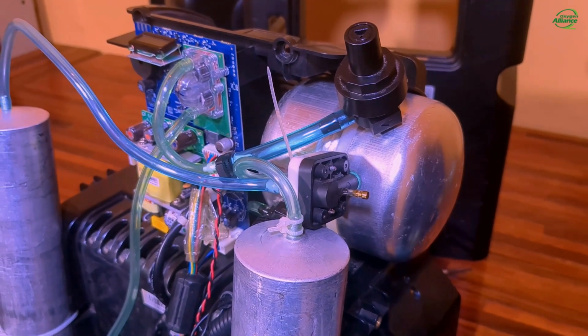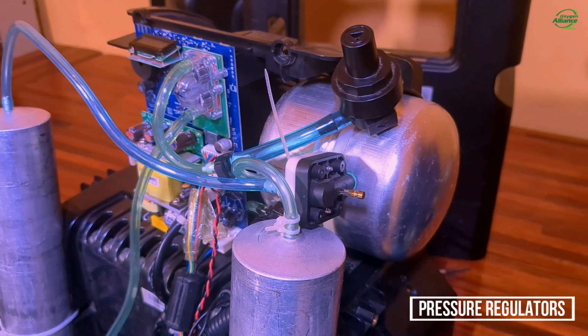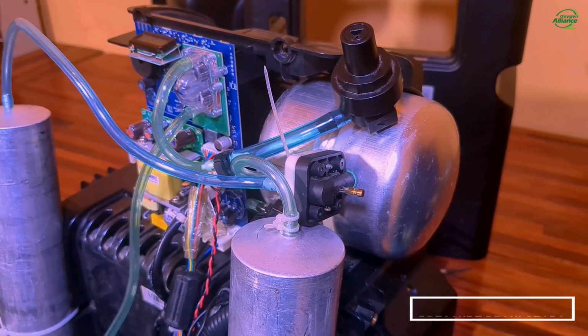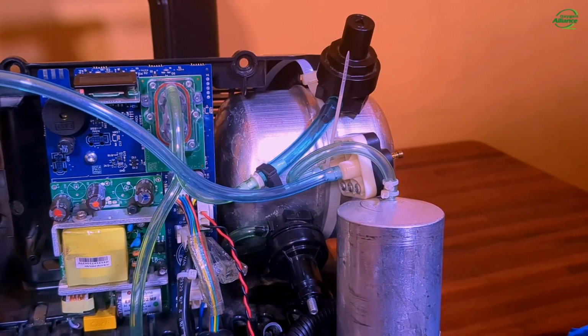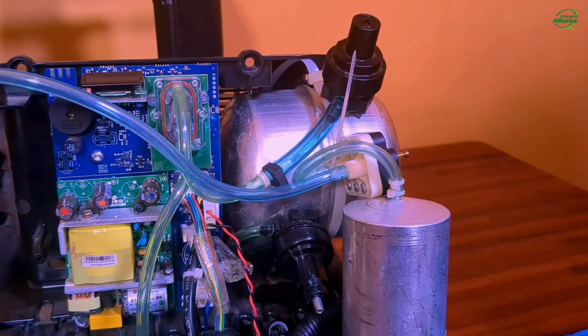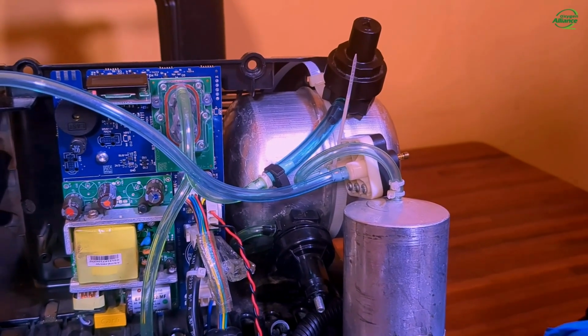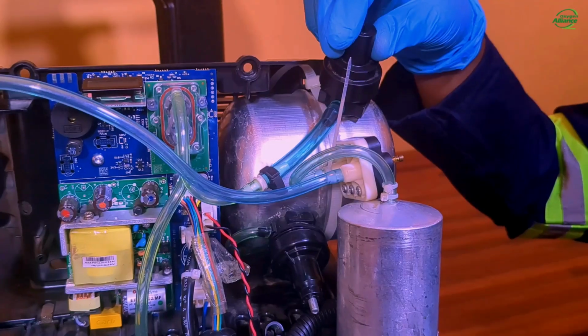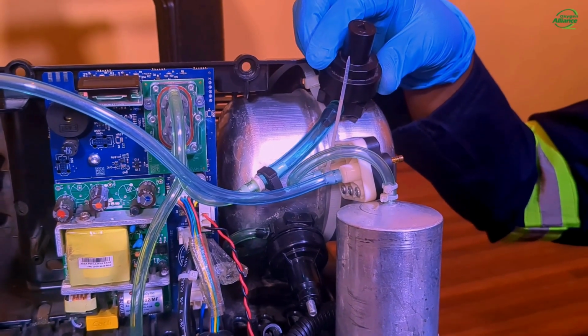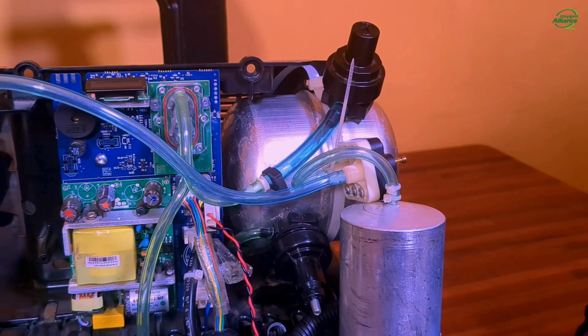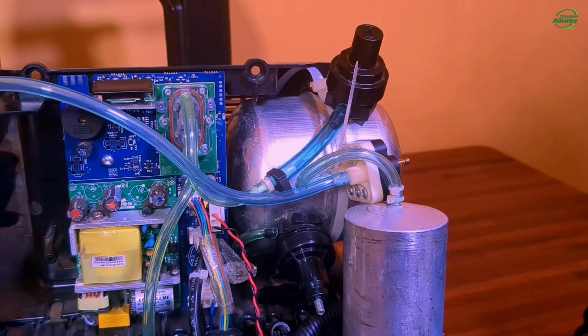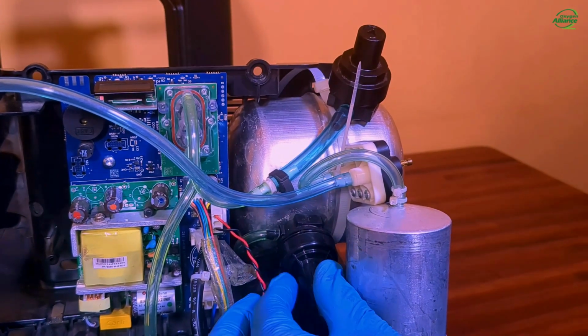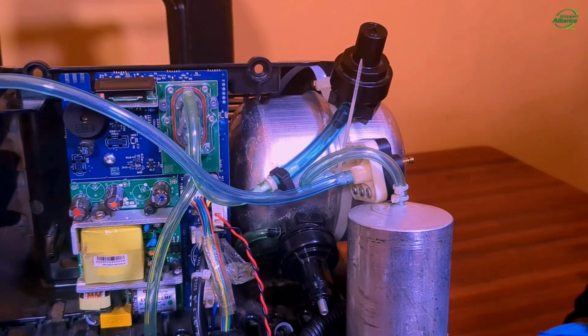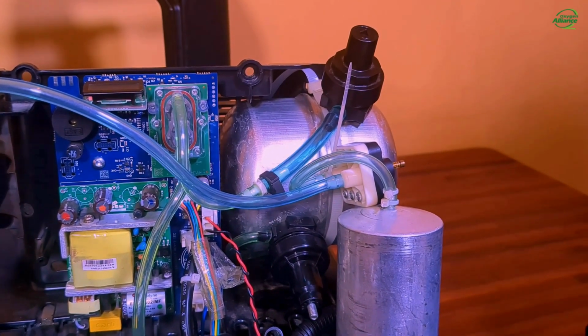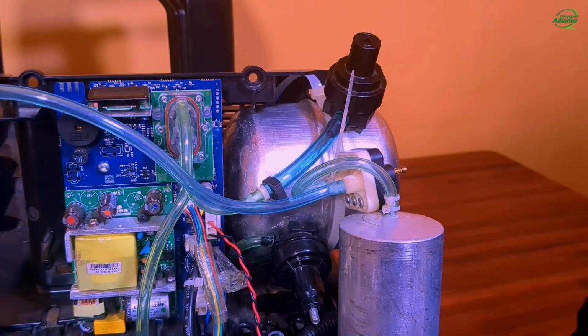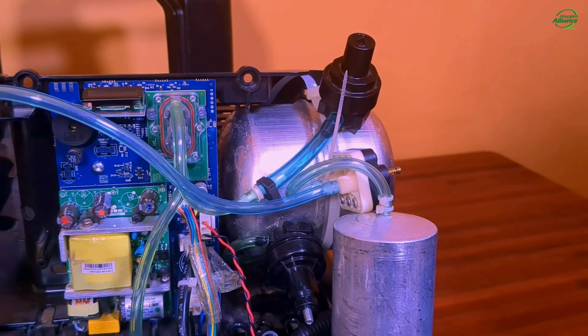And next, we have the pressure regulators. So the 1025 has got two pressure regulators, one that controls pressure that is going to the patient and one that goes to the auxiliary oxygen port. So this one right here controls the oxygen that is going to the patient, and the preset value is 20 psi or 138 kilopascals. This one over here controls the pressure that is going to the auxiliary oxygen port, and the preset value for this pressure regulator is 15 psi.